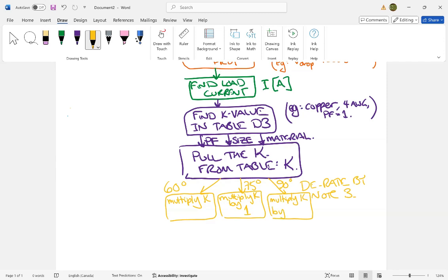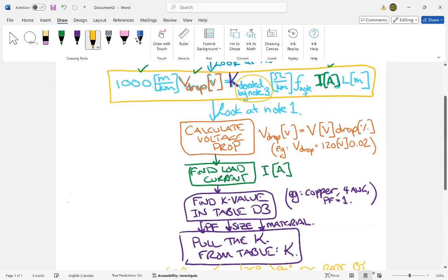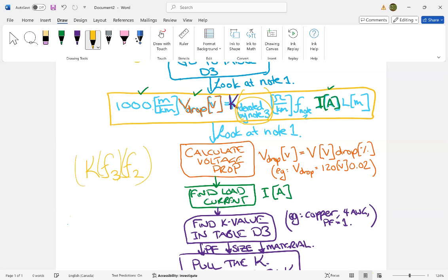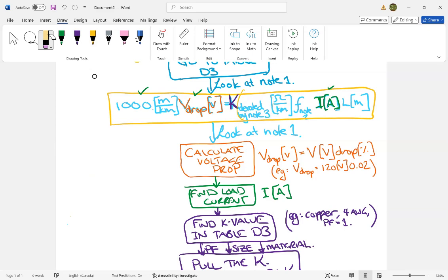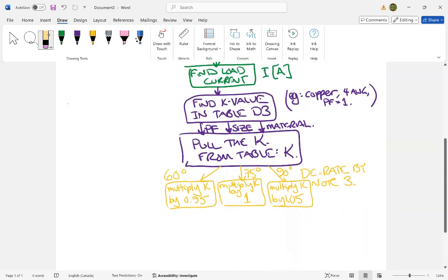Okay, if it's 90 degrees, you'll multiply it by 1.05. If it is 60 degrees, then you're going to multiply K by 0.95. So it's a little bit silly. I think it really should be another thing on here. It should have like K times a factor of note three times a factor of note two. But it's not really like that. It's just like K derated by a factor. Maybe I should redo this equation and have it differently. But anyway, K has to be derated by note three.